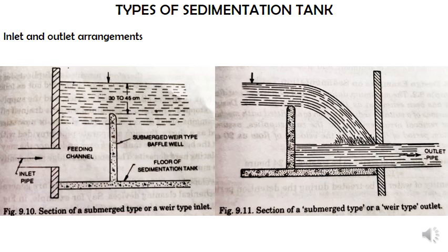Okay, so the inlet and outlet arrangements. As I told you in the previous slides, whether it is an inlet or an outlet, we always have a baffle. You can check it out over here. These baffles are provided, for the inlet as well as the outlet, because we make sure that once the water enters here, it is not going to disturb the water which is already present in the unit. So these inlet and outlet arrangements are the same for all the treatment units. It is not only for the sedimentation tank.